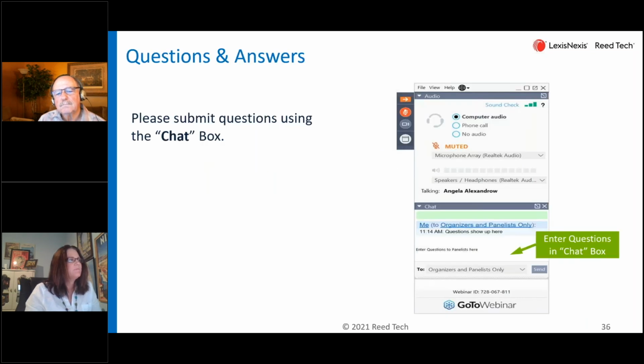Prioritizing. If you have many legacy devices, first question, should you prioritize registering legacy devices, or should you concentrate on getting your equivalent MDR devices certified and registered? Yeah, I think that question refers back to that little transition timeline that we had up, where some companies are doing what they can inside the constructs. So I would think it's a good strategy to go ahead, emphasize getting your legacy devices registered.